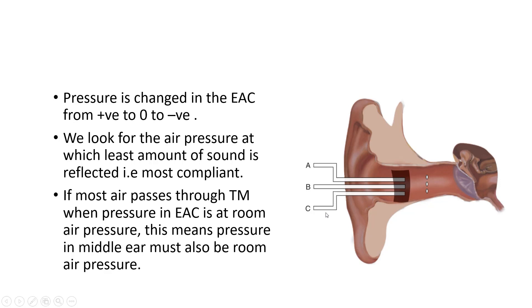When does the most amount of sound pass through the tympanic membrane? When the pressure in the external auditory canal matches with the pressure in the middle ear. In a normal ear, the pressure in the middle ear is equal to the pressure in the atmosphere — atmospheric pressure or 0 atm. When we apply 0 atm pressure, the compliance is maximum and most of the sound is passed through, or the least amount of sound is reflected back.